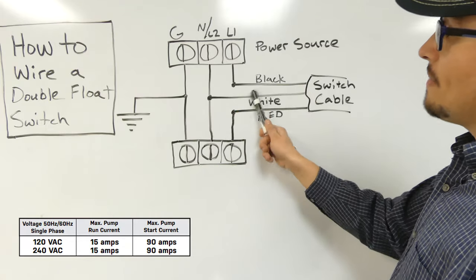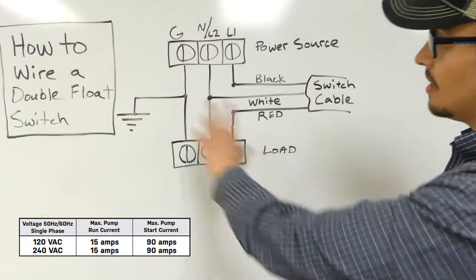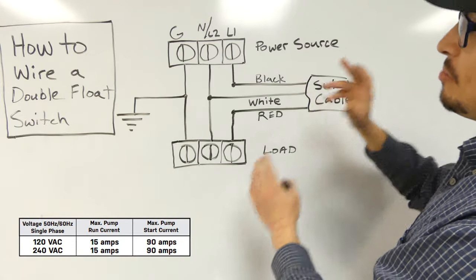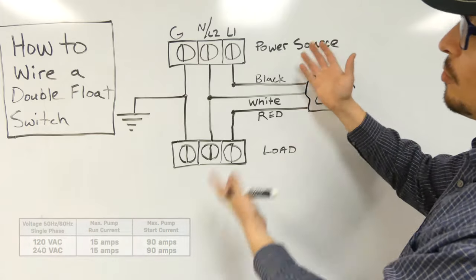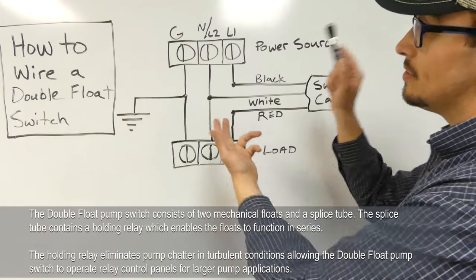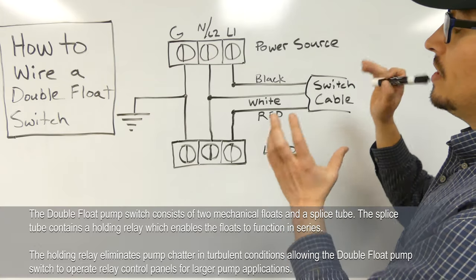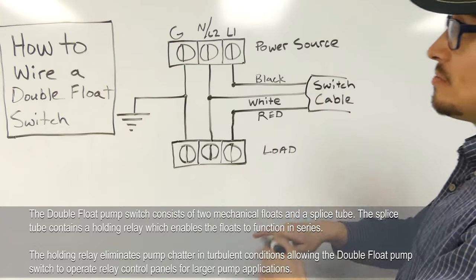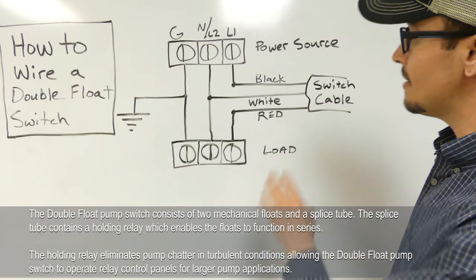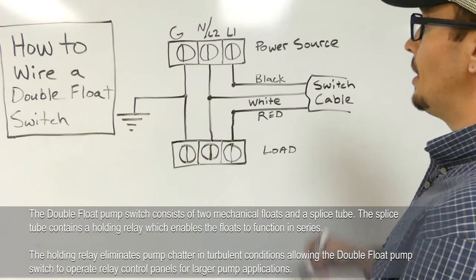But the thing to remember with a double float switch, big warning, double float switches, you have to purchase the one appropriate to the voltage you're using it on. So we sell 120 volt and 240 volt double float switches. You have to buy the right one for the particular voltage you're using or it will not work. And that has to do with the relay that we just talked about.